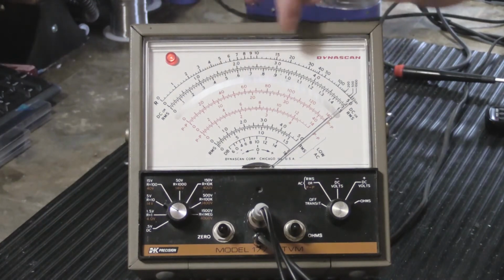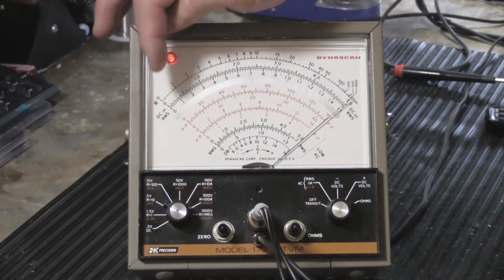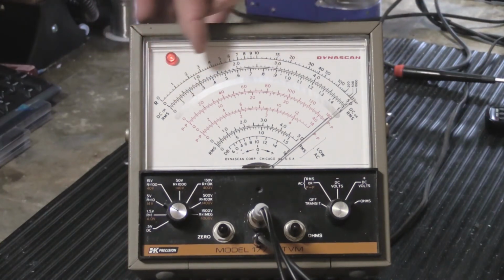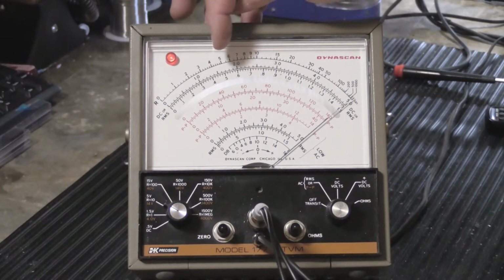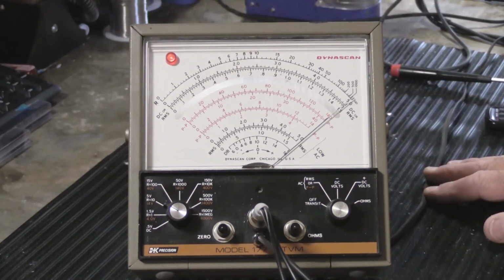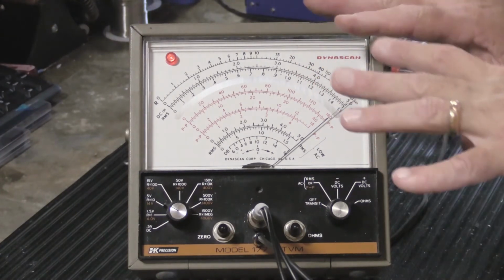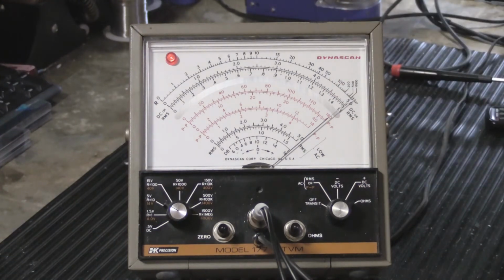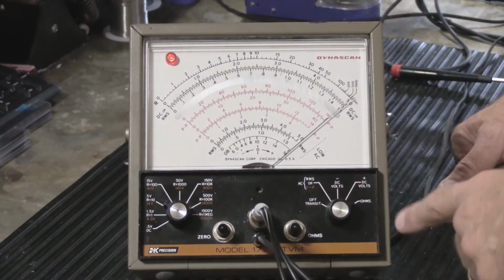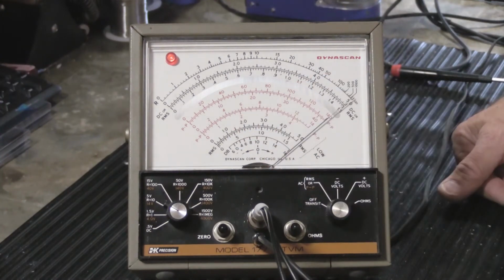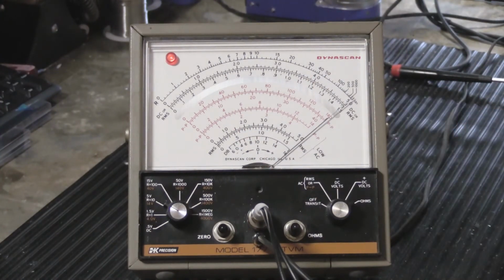Now, when we moved the range switch and things moved around a little bit and we went to the times 100 scale, went up here, and then back to the times 10 scale, it didn't quite go above the 5 like it originally was. It sort of settled in on the 5. So why would that be the case? Well, a couple different things. One, nothing's been done to this. This is how it came out of the box. So the switches all need to be cleaned, and maybe a little bit of work needs to be done inside. But we'll get to that in just a minute.